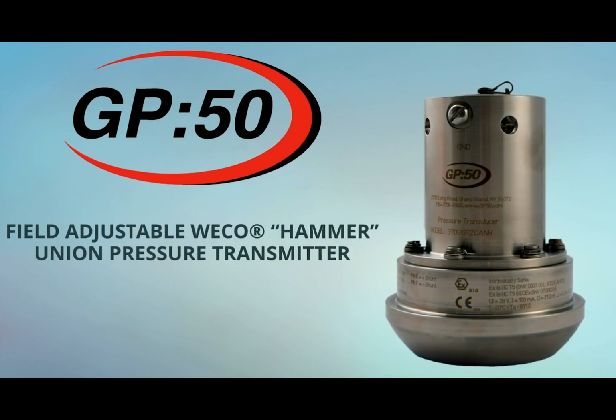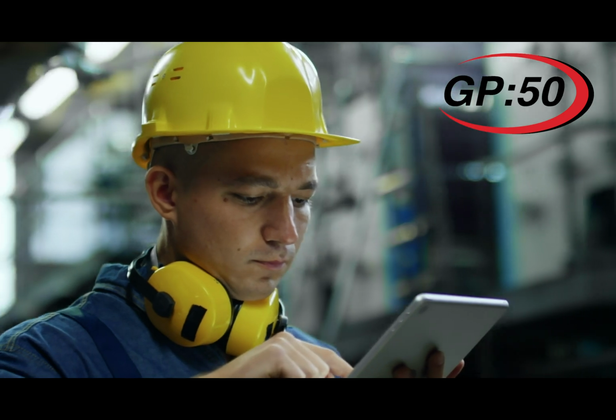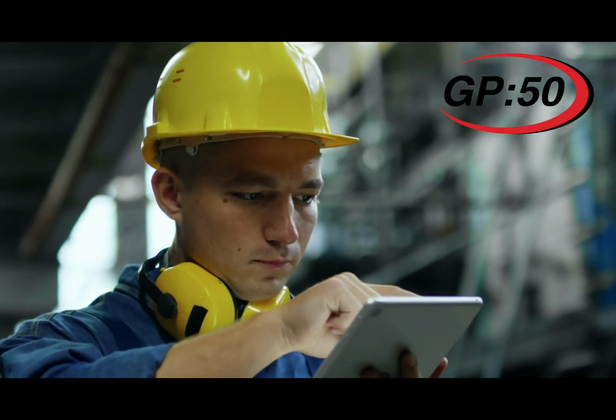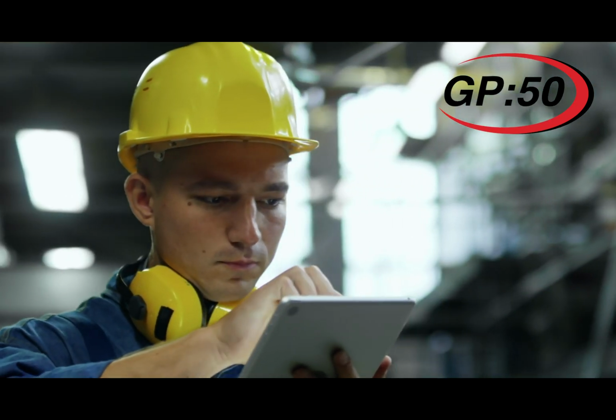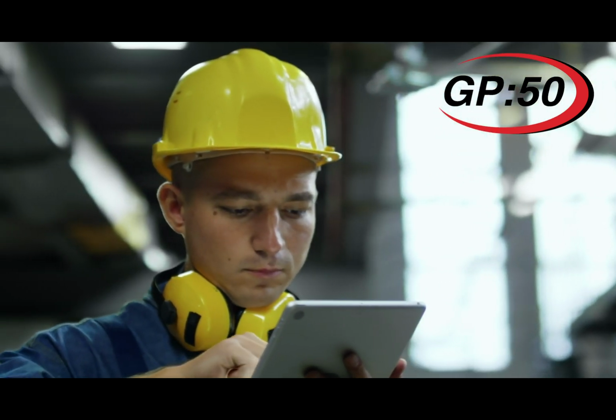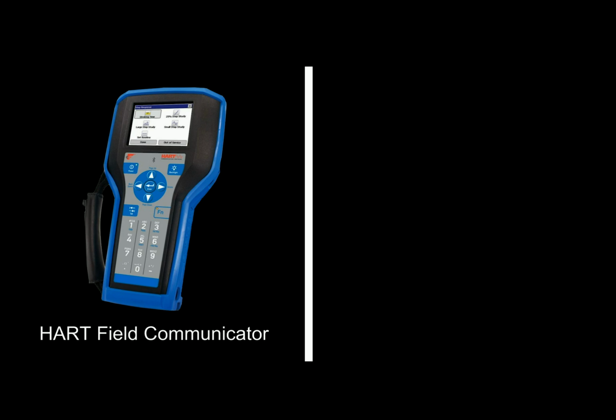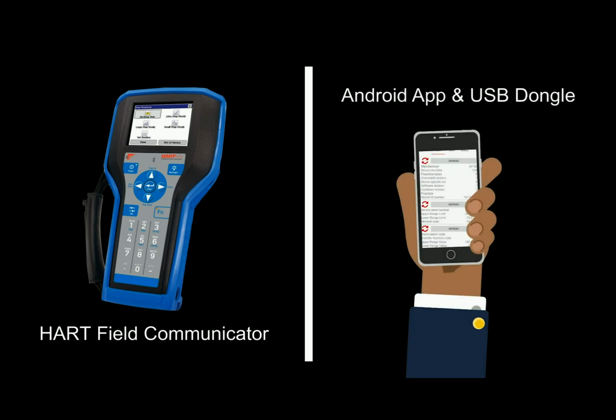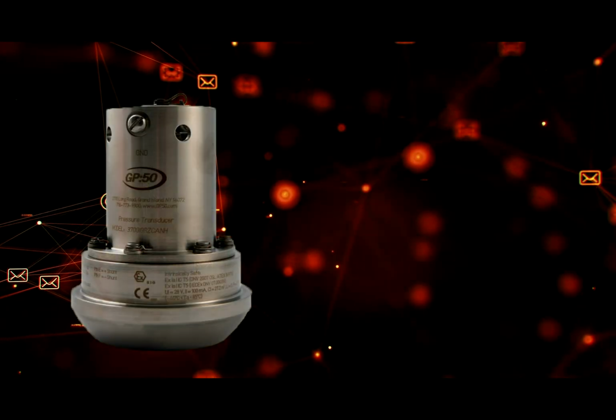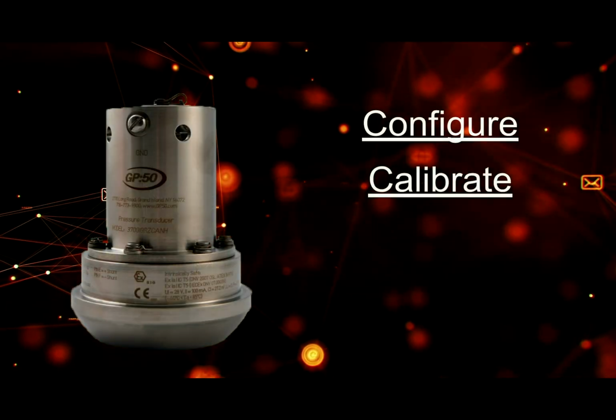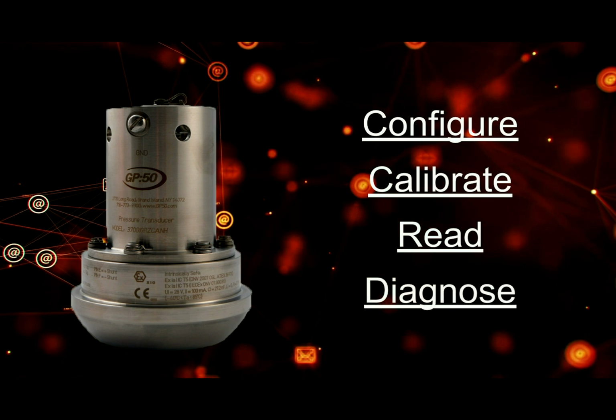GP50 offers a variety of digitally field adjustable products, including the Model 470 field adjustable WECO hammer union pressure transmitter. Units like the Model 470 allow you to configure the transmitter using your computer's USB port with a HART dongle and a free GP50 software program. You also have the option of using a HART communicator as well as an Android-based app coupled to the USB HART dongle. The GP50 software allows the user to configure, calibrate, read, and diagnose the device.